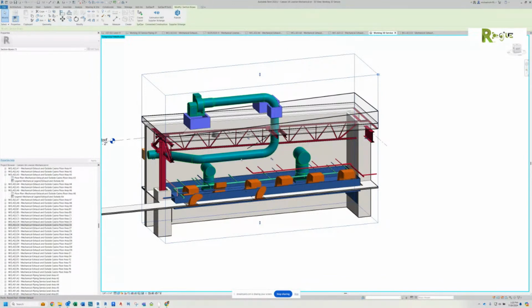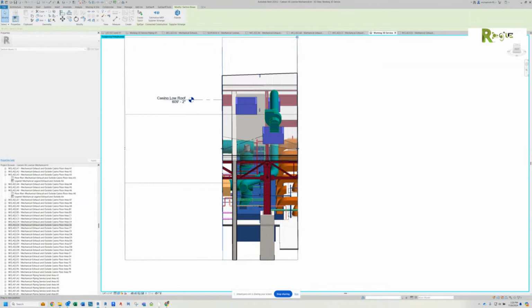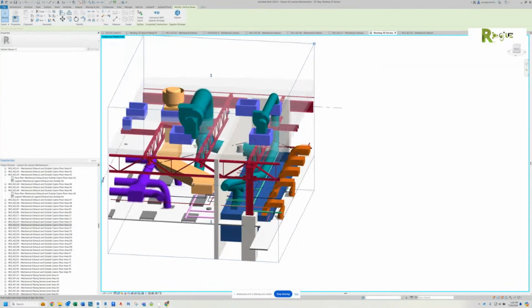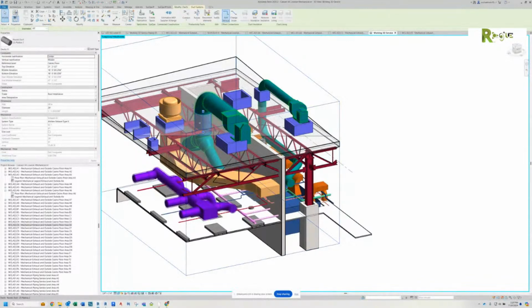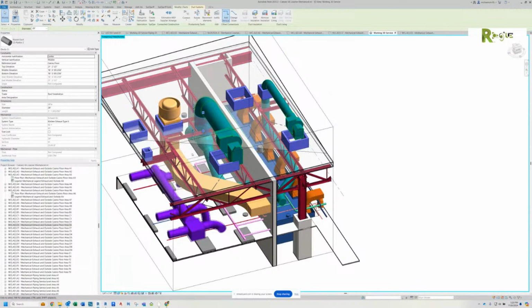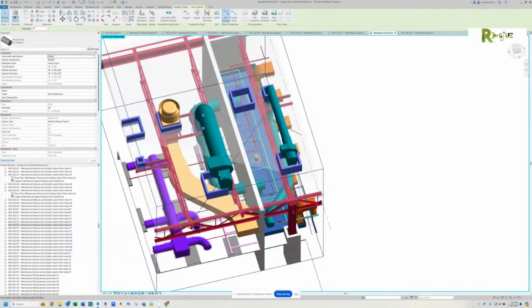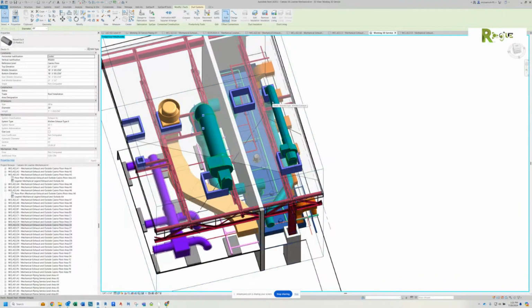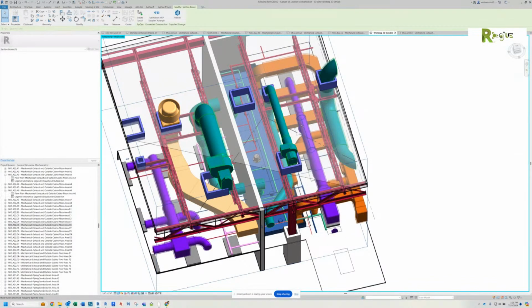Not that one. Stretch your section box. That one, yep. Oh, the other fan. That's the hole that he was trying to hit. He's saying that hole doesn't have the steel in there. Nope. What about the regular exhaust? You see that steel there that has nothing in it to your right? Go up. Yeah, right there. So that's where it shows the steel beam, but there's no steel there directly above the hood, so it'd be a straight shot out.